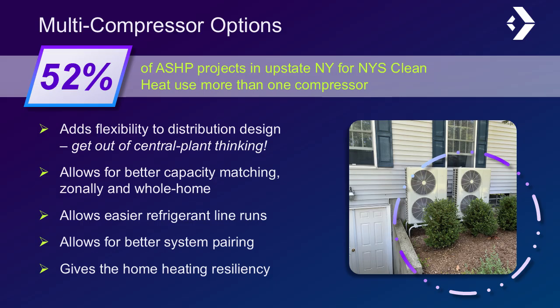Multi-compressor systems are gaining traction in heat pump design, with 52% of air source heat pump projects in upstate New York for New York State Clean Heat now incorporating more than one compressor. These systems bring a range of benefits, including greater flexibility in distribution design, improved capacity matching for both zonal and whole home needs, and simpler refrigerant line runs. They also enhance system pairing and provide heating resiliency, ensuring reliable performance even in tough conditions. While multi-compressor systems may come with a slightly higher upfront cost, the increase is often smaller than one expects, making them a smart and valuable choice for many projects. For more information on branch boxes and multi-compressor systems, contact your manufacturer or wholesaler.